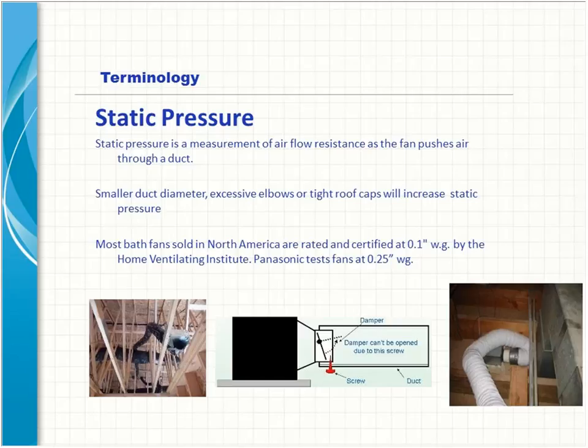I was at a job site in Seattle 6 or 8 months ago, and the ductwork was connected with 3 mechanical fasteners by code, and all 3 of those screws were installed in the bottom, and all 3 of them were installed so that they would conveniently hold the damper on the fan shut. So you can imagine the performance issues, and we were called to the job site due to performance issues. And we found that not only was the wiring wrong and the exterior termination painted shut, there were 3 screws in all 150 fans holding the damper shut.